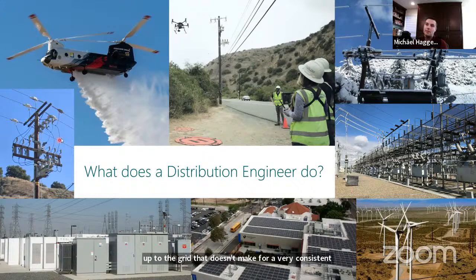Here we have an RAR, the same one we saw earlier. We propose new areas for RARs where we can improve reliability in certain areas, and we also propose the initial settings as distribution engineers. Whatever the normal loading is on the circuit, say 100 amps, we do not want the RAR to trip on normal loading. We only want it to trip if there's a wire down, which is like a phase to ground fault, and you'll see the amps on that circuit shoot way up from a normal 100 amps to over 1,000 amps in this particular instance. When this device sees that jump in the amps, it immediately opens and turns the power off to that fault.